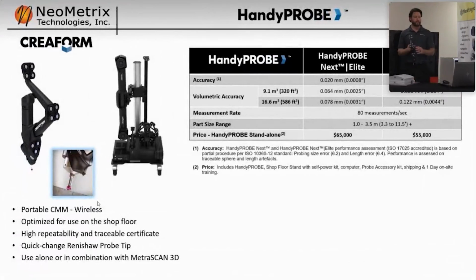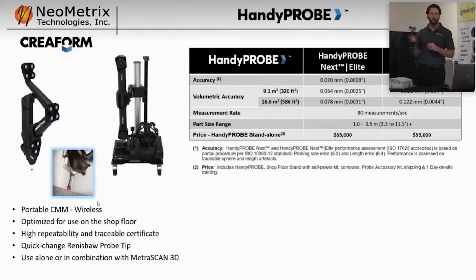Okay, some accuracy specs: single point accuracy of this probe here. You can see there 8/10,000ths, or 20 microns, so less than a thousandth of an inch, single point with our field of view. Volumetric accuracy: we've got two different volumes we can work with, 9.1 meters cubed and 16.6 meters cubed. I generally just run the larger one. It gives me a huge field of view, and I only give up about 0.5 or 0.6 of a thousandth of volumetric accuracy. So anywhere I probe point to point across the distance in that huge field of view, I have an accuracy of 78 microns, or just over 0.003 of an inch. So that's huge.